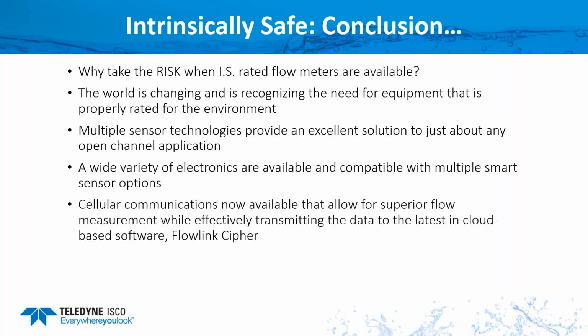And then we offer the cell phone communications, which is now available in the intrinsic safe equipment. We've always had it for non-IS equipment, but now it is available. So it provides superior flow measurement while effectively transmitting the data to our latest cloud-based software, FlowLink Cipher. Or you can sit in your office, call up the sites, download the data, and it allows you to get alarming from the modems. If you have a high level or high flow alarm, you can have the instrument text you immediately to know that an event is occurring.